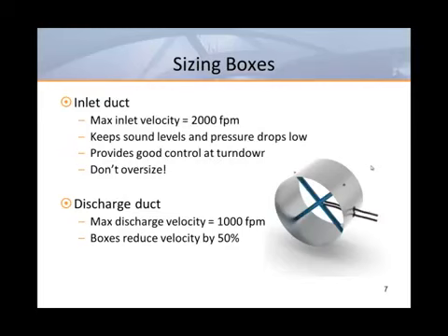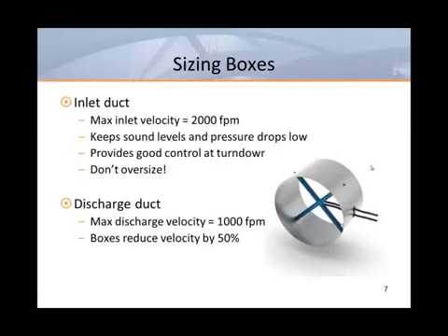As far as discharge duct work, I like to think of boxes as devices that reduce velocity by 50%. If you have 2,000 feet per minute going in, you shouldn't have more than 1,000 feet per minute coming out. Discharge duct work should therefore be sized for no more than 1,000 feet per minute. In cases where grills will be tapped directly into the sides of the discharge duct, I would design for no more than 800 feet per minute to prevent the possibility of room air being induced into the first few grills.